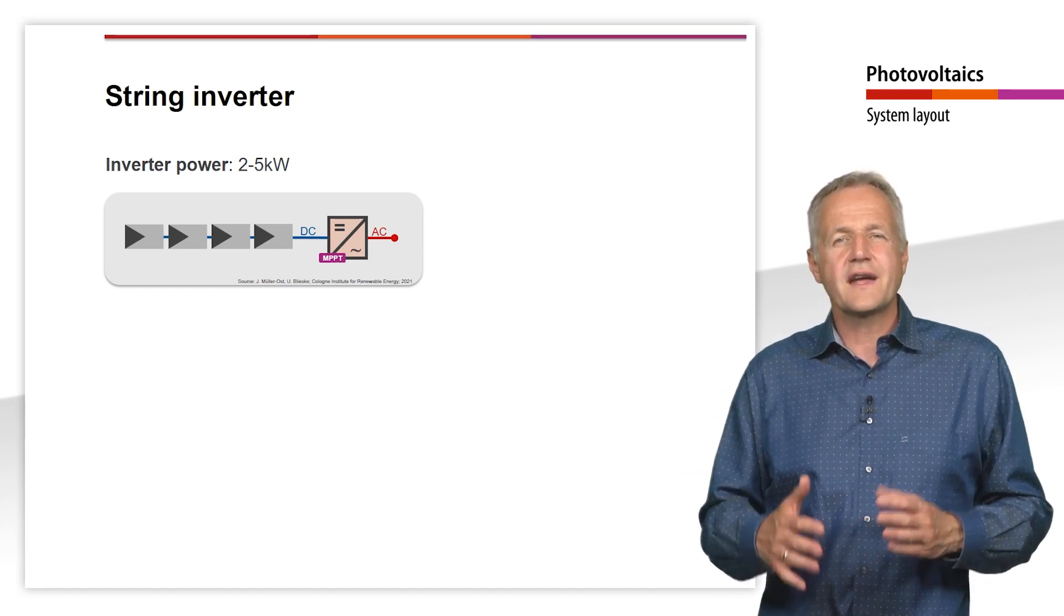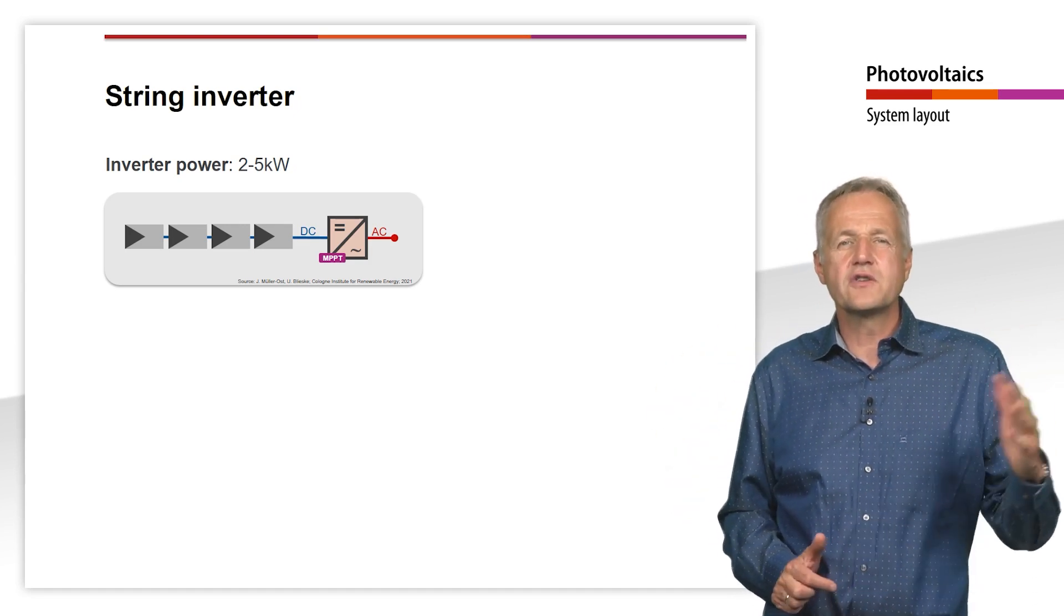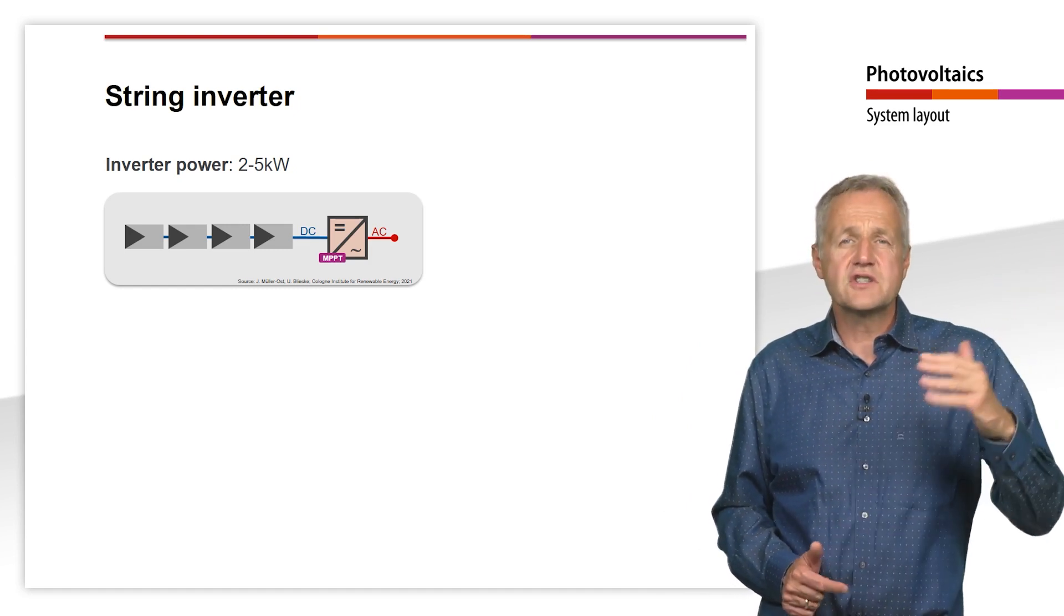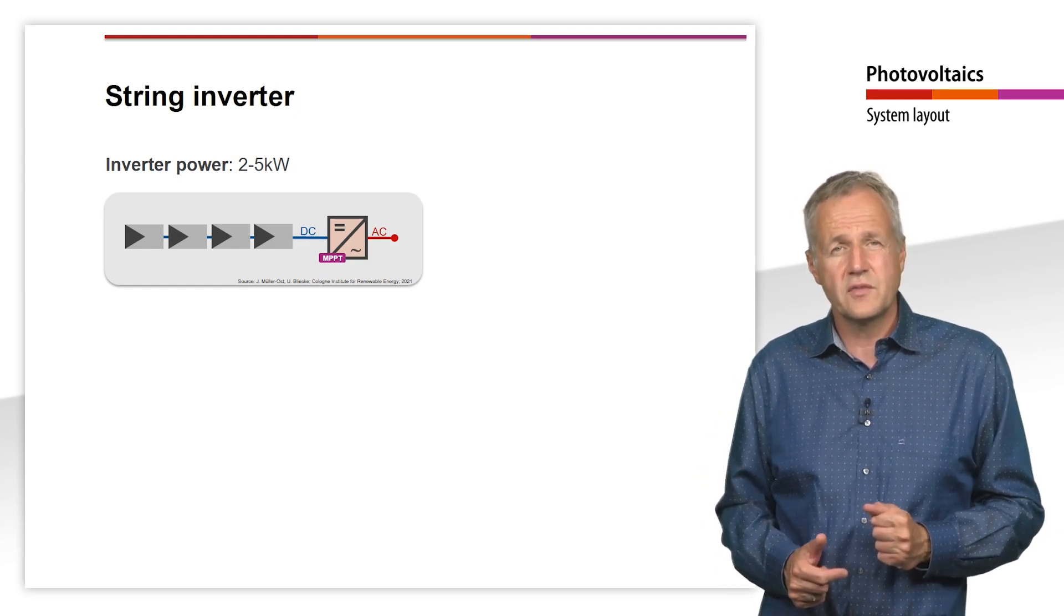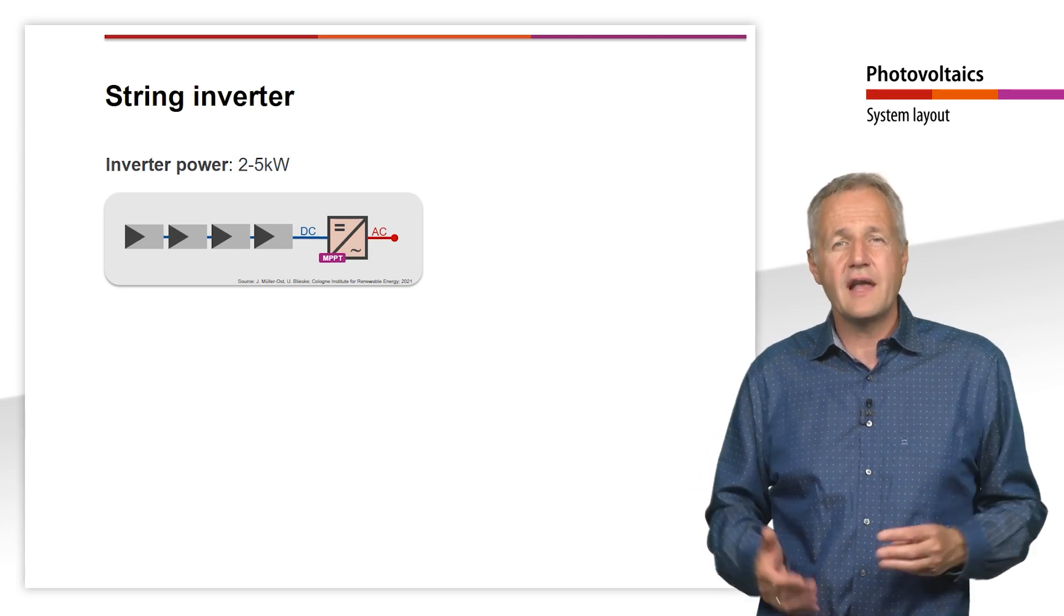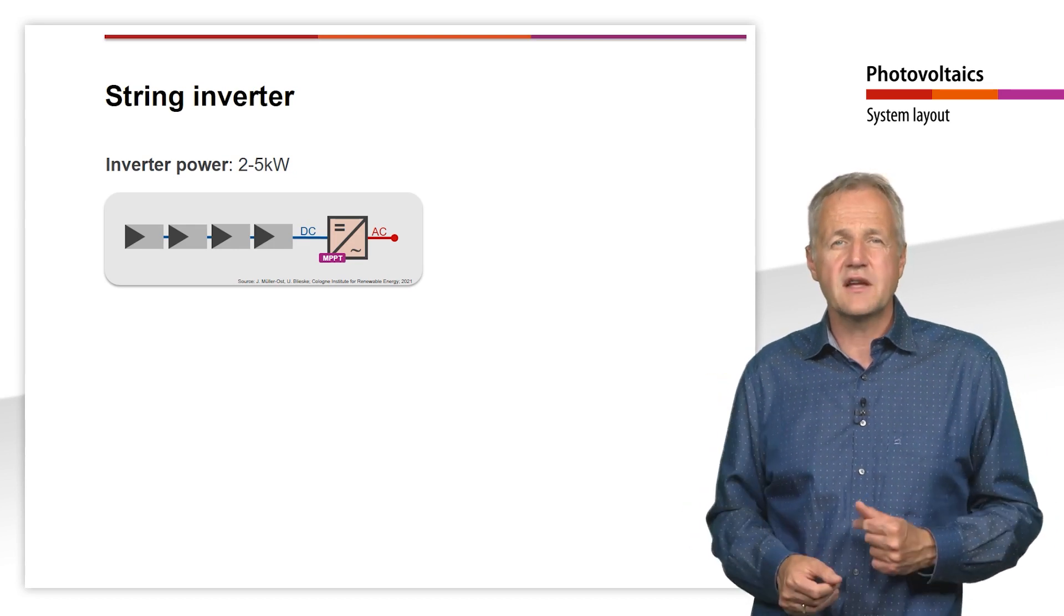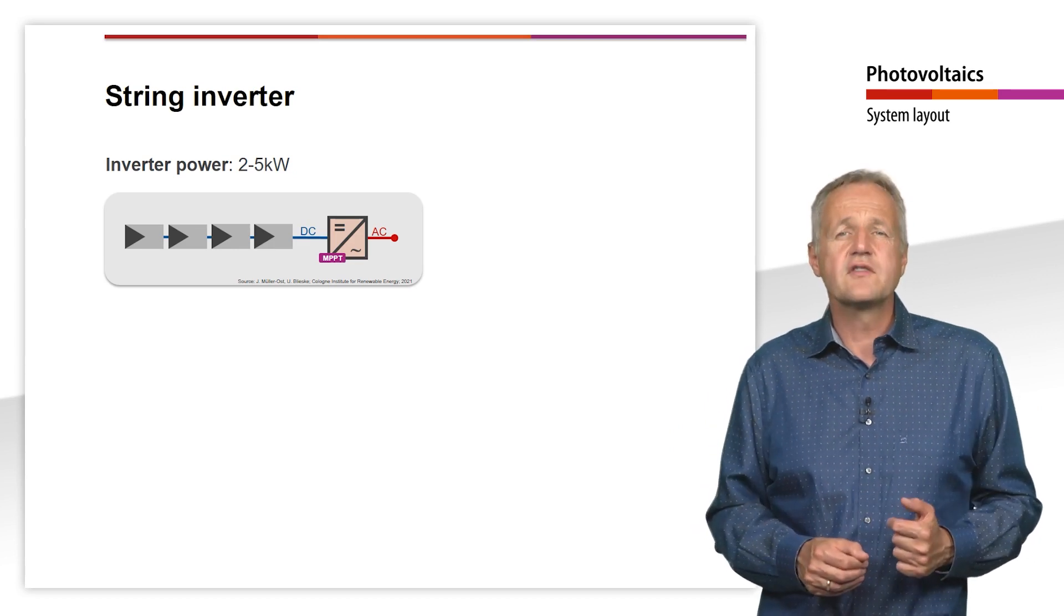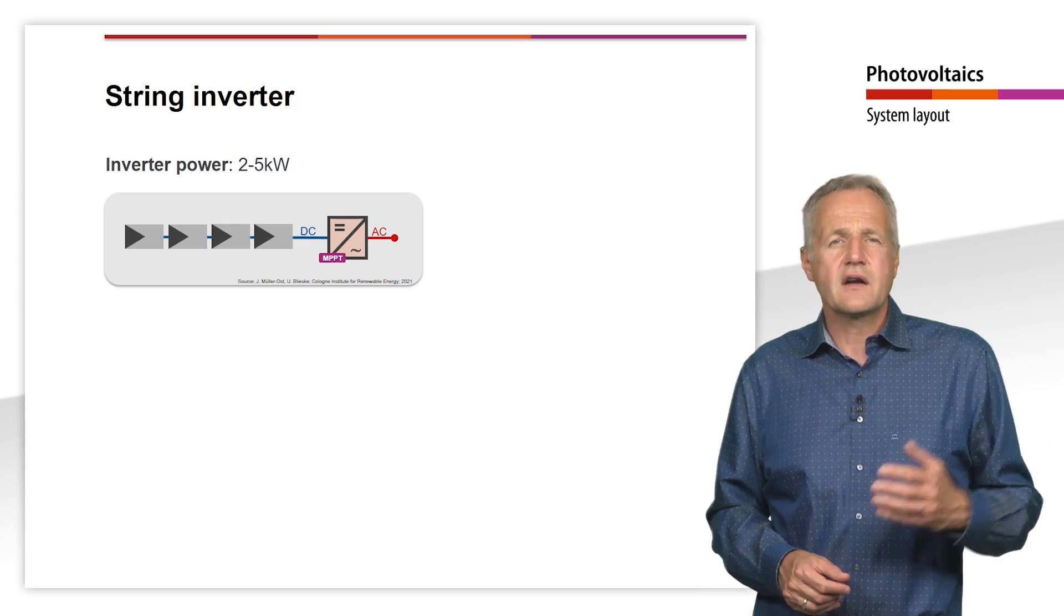Modules are therefore connected in series whenever possible. By connecting the modules in series, the module voltages add up and quickly lead to voltages of up to 1500V on the DC side of the system. Since DC voltages of 120V and above are life-threatening, various safety precautions must be taken above this value, for example double insulation of the cables and the modules. The regulations for these are country specific.